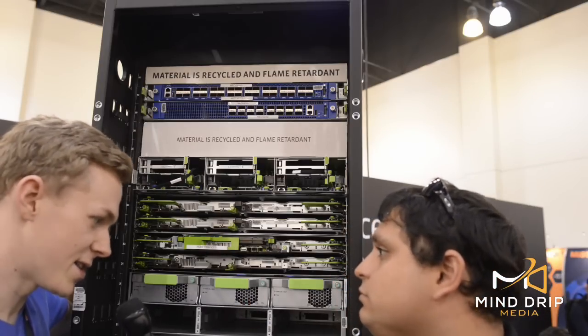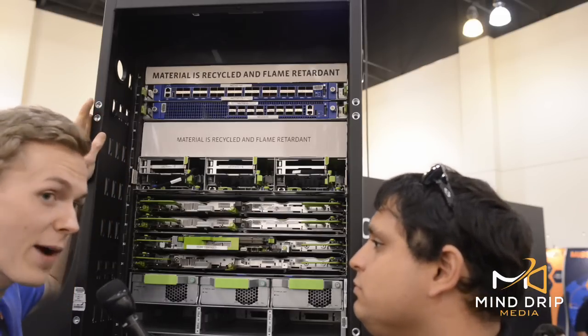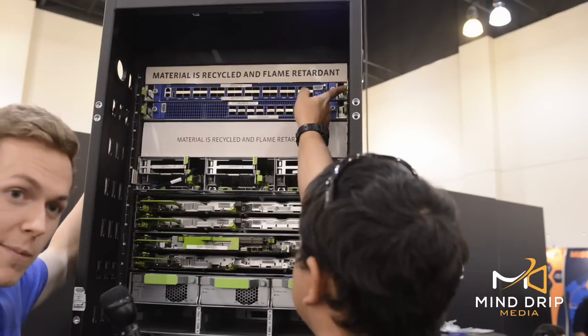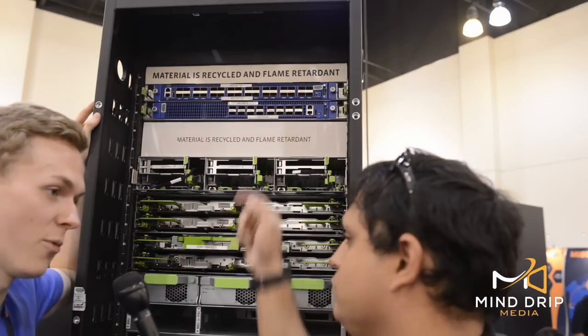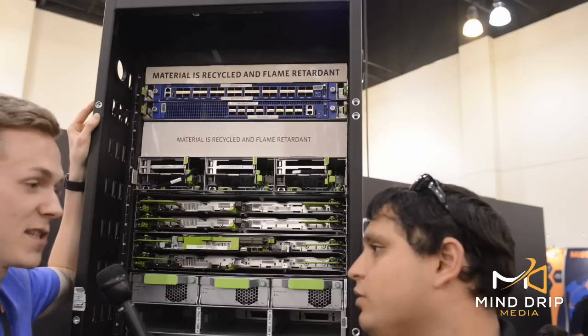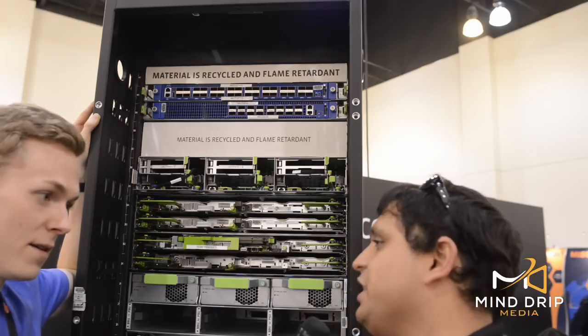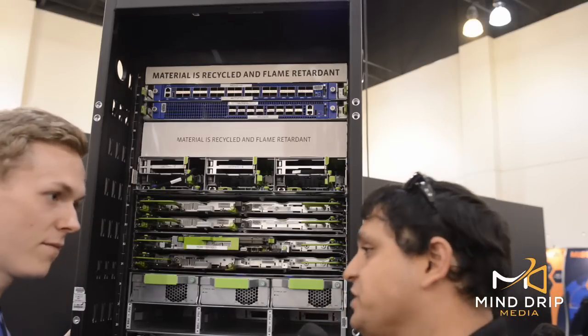Yeah, so what's interesting is they've actually adapted the power supply modules so that it'll pass the DC from the back of the rack, back of the power poles that we just saw before, straight through into the switch without requiring the inverter to AC and then rectifying back down at the switch level. And the switches aren't just normal switches, they're actually white label switches that are designed with open standards as well.